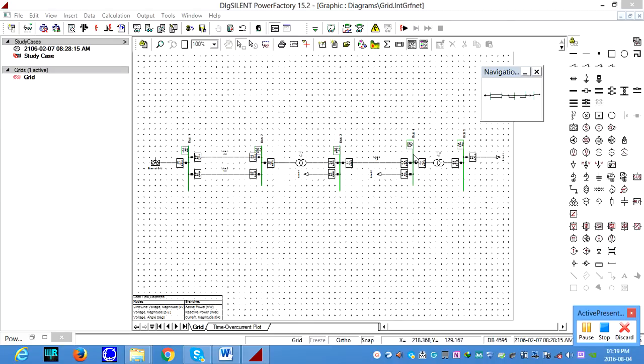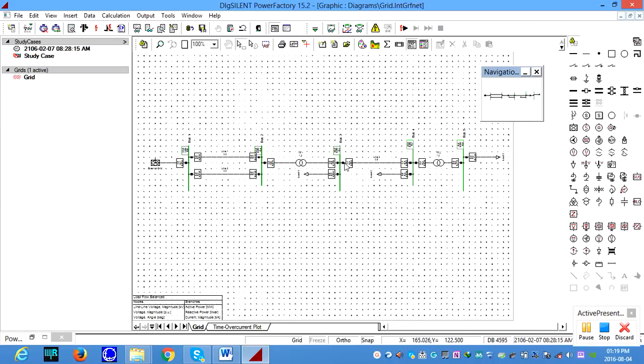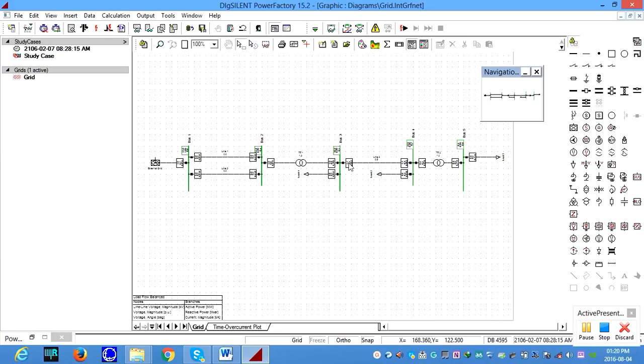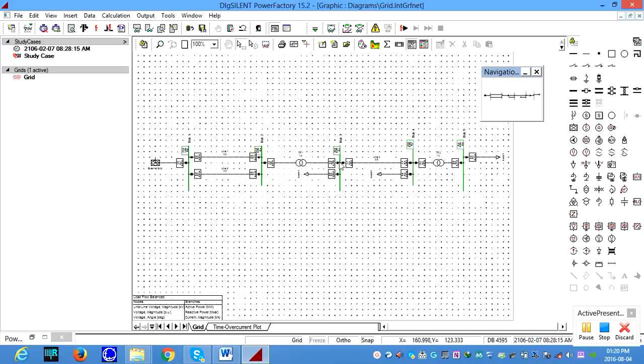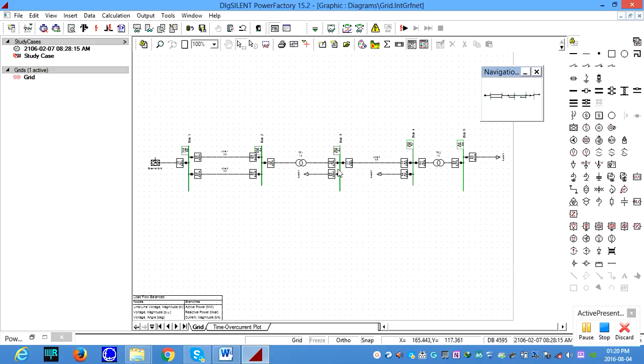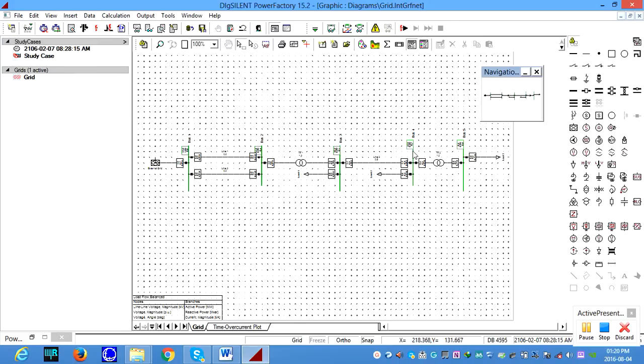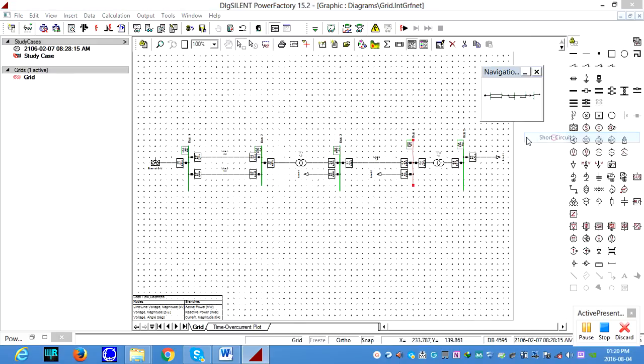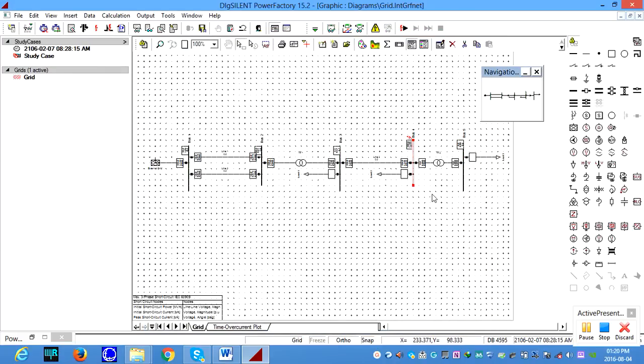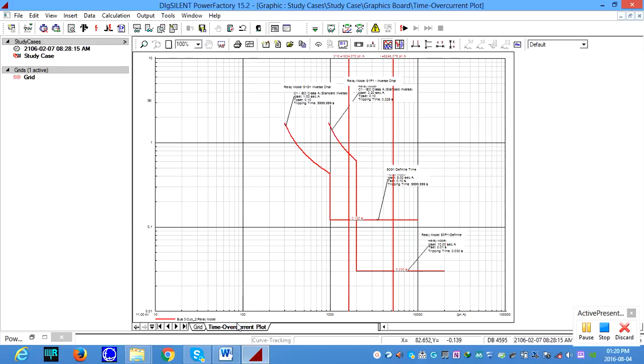Okay, now you need to apply a fault on bus 4, where the relay is sitting. The direction we didn't set, it's non-directional, which means if you apply a fault on bus 4, it trips. The relay is sitting here, so for any fault further downstream, this relay will trip. But if the fault is upstream, the relay will not sense it, because we have not configured the directional one. It's a non-directional one. So apply the fault on bus 4, short circuit, IEC method 3-phase fault, execute, and verify the tripping characteristics in the time-overcurrent plot.